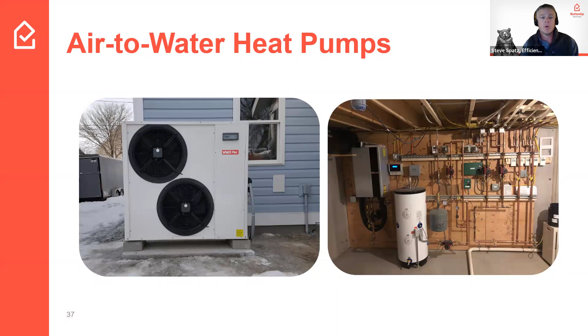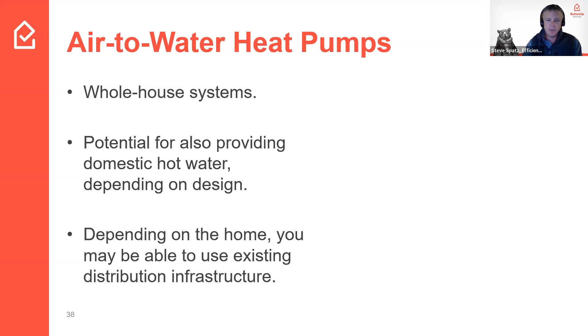With this type of equipment and with the right design, it is possible to do domestic hot water off of the heat pump as well. So again, thinking about this, if you have a boiler in your home right now, an oil or a gas-fired boiler, and you have an indirect hot water heater off of the boiler, the thermal storage tank off of that boiler, the same type of concept of design can be put into place with an air-to-water heater. It takes careful design and a few layers of process, but that's capable with this type of equipment. And there are considerations that come into play again about what you can do and what you can't do with the existing distribution you have in your home.